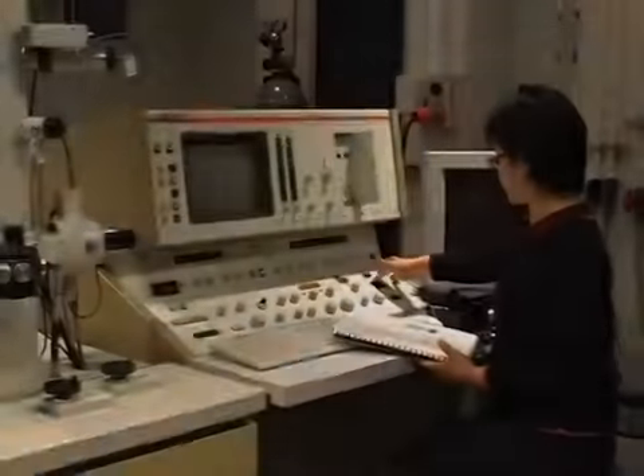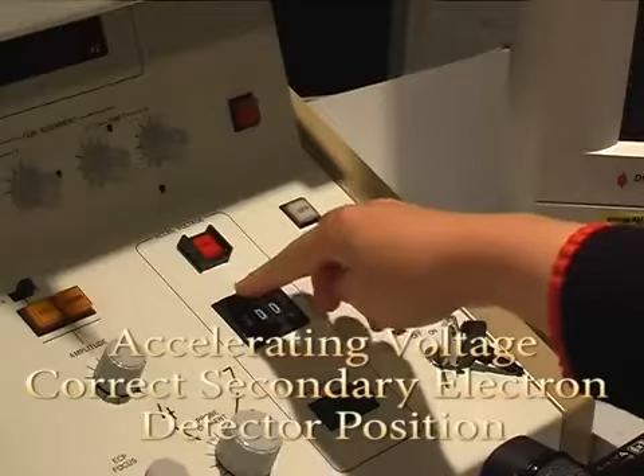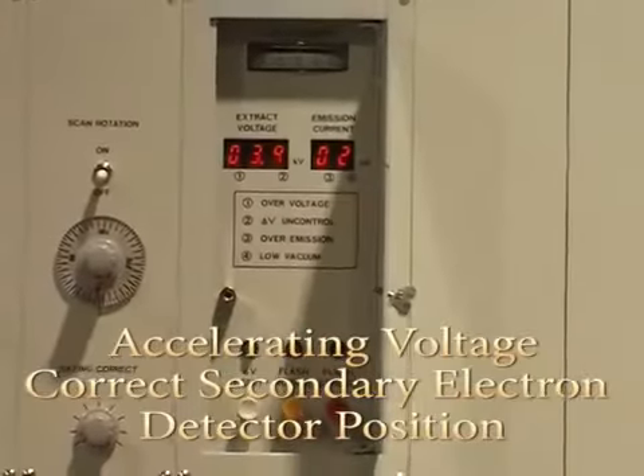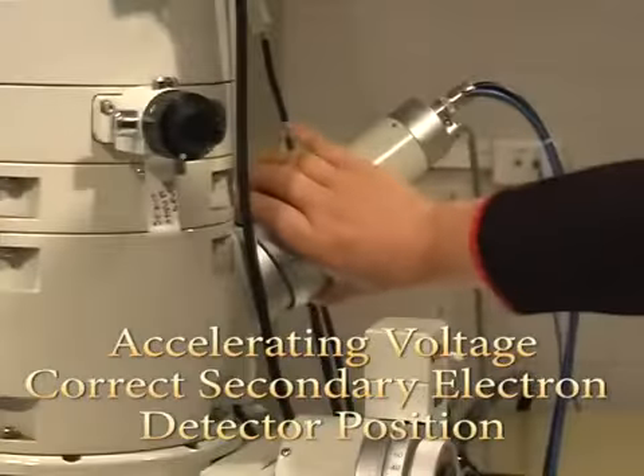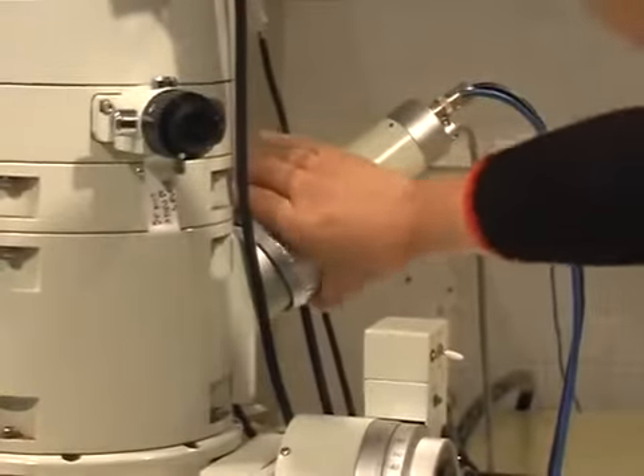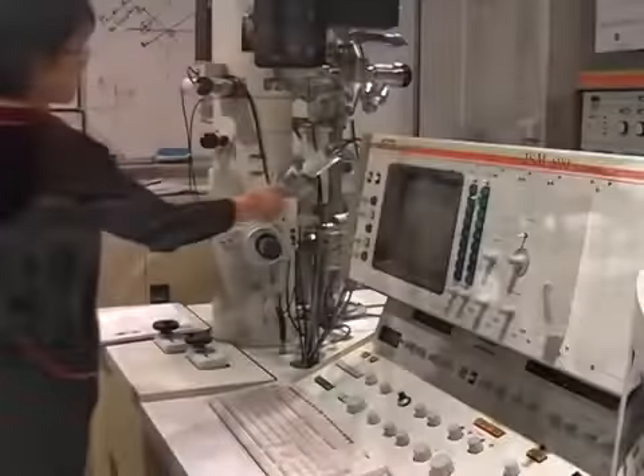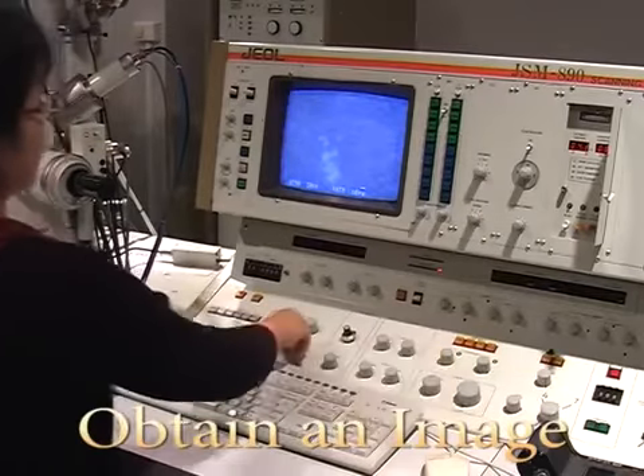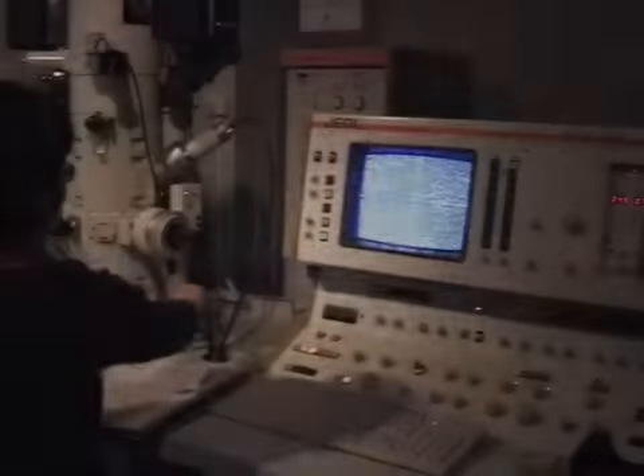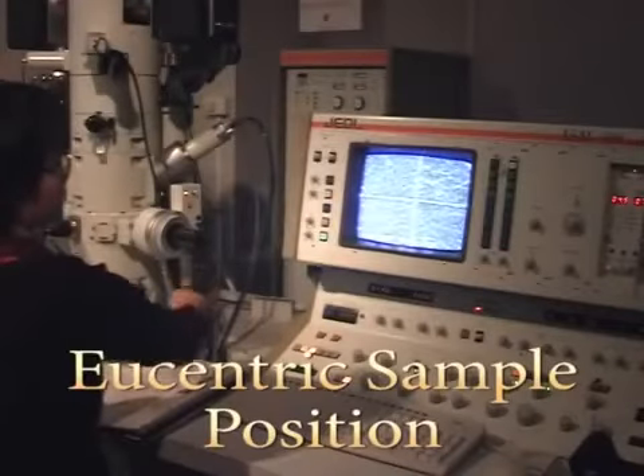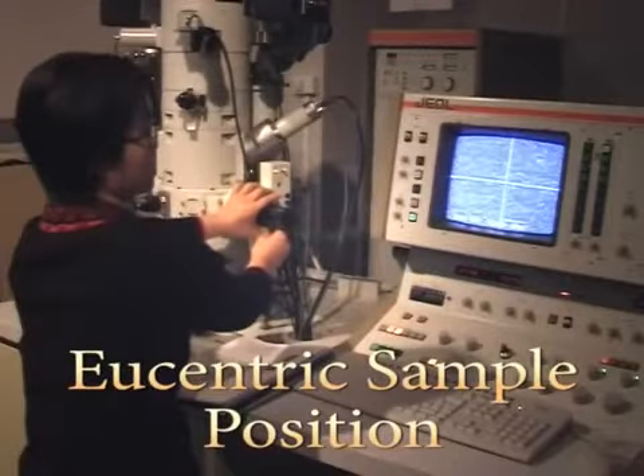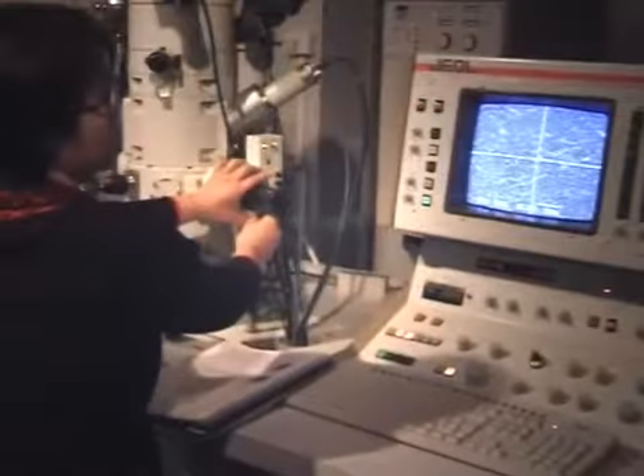within the microscope. With the accelerating voltage turned off, adjust the accelerating voltage, then turn on the accelerating voltage. Position the secondary electron detector for the kV you require. Open valve V7, use coarse focus, then fine focus to get the best possible image of the specimen. Release the goniometer motor. While tilting the goniometer back and forth, rotate the specimen height control knob. Adjust the goniometer back to 0 degrees tilt. Reapply the goniometer motor.